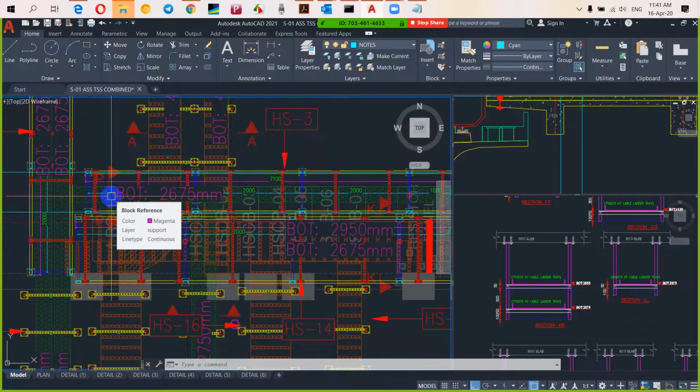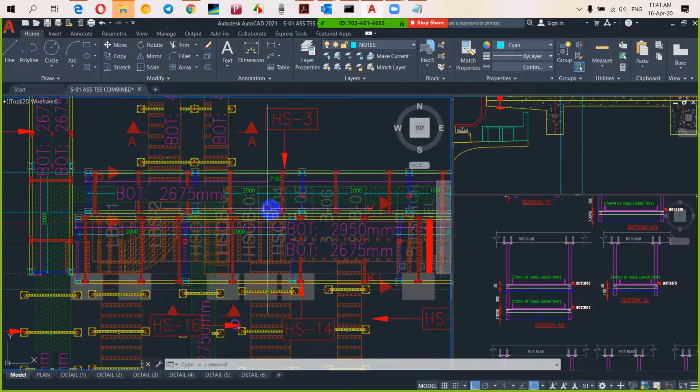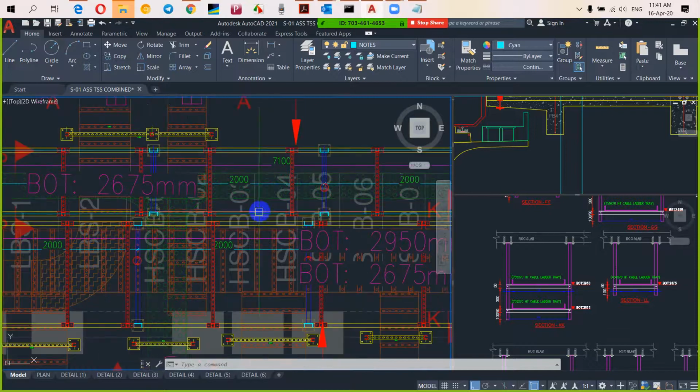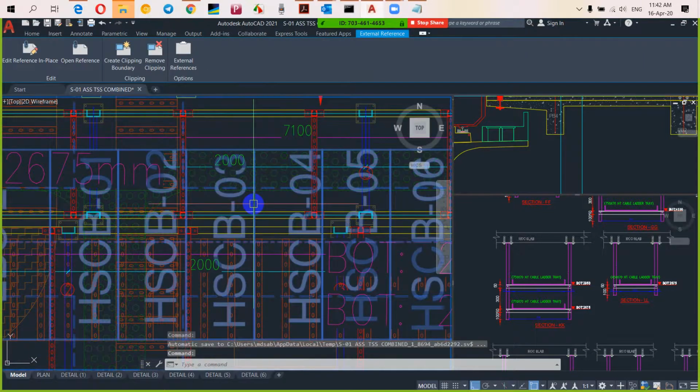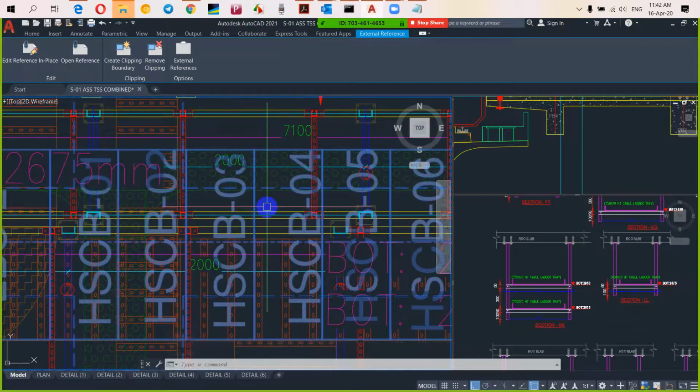Above the 1.5 kV DC switchgear, the LT tray position, they would like to shift it 200 towards the 33 kV switchgear. Is it okay or not? If it is shifted, then it will be out of the HSCB, no? Jamil, actually they are going to shift only the support, I guess, not the cable tray. The cable tray location will remain the same. Only the support they are going to shift, maybe. The cable tray will be moved 50 mm or 100 mm.